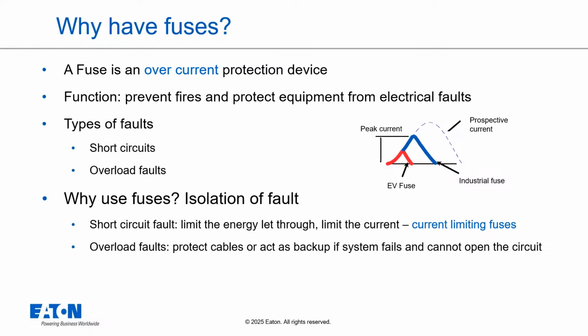For overload faults, fuses protect the wiring or act as a backup if the primary protection system fails to open the circuit. This graphic shows a typical industrial fuse in blue and an EV fuse in red, illustrating their time current performance differences. The key takeaway here is that EV fuses are designed for much faster and more precise interruption performance compared to standard industrial fuses, especially under fault conditions.